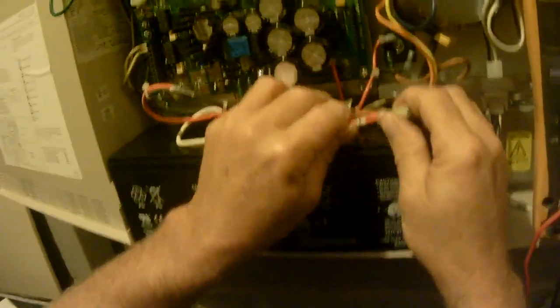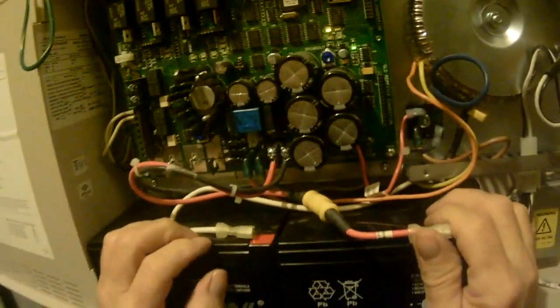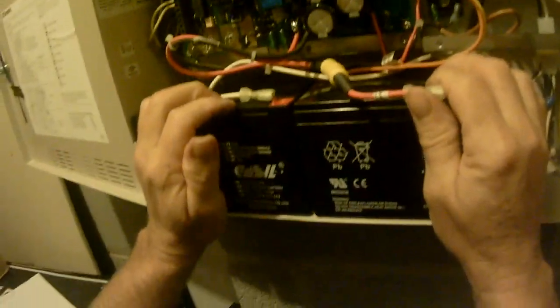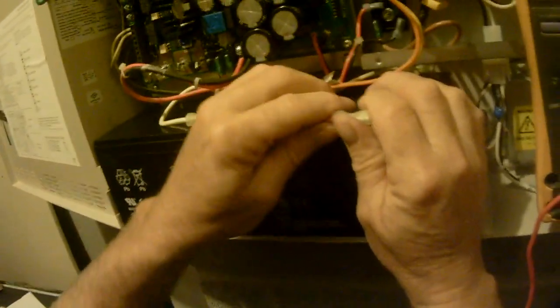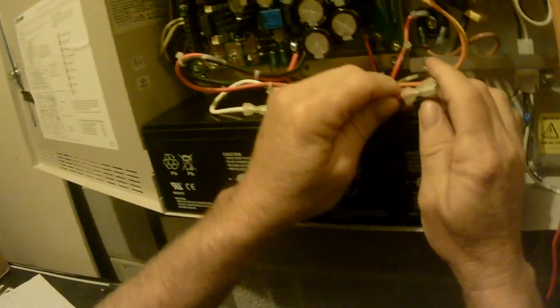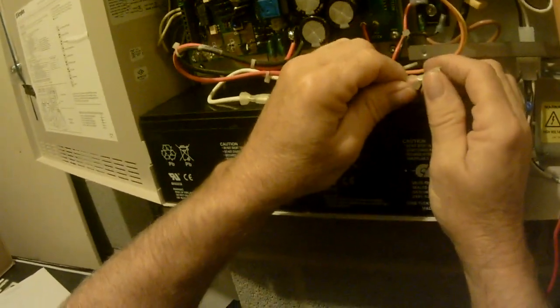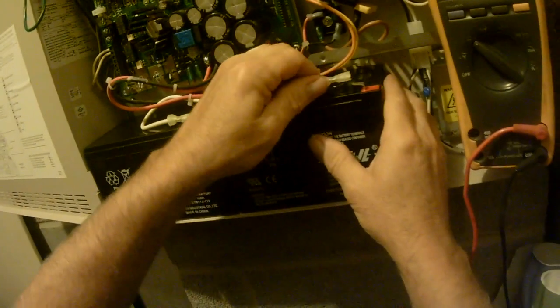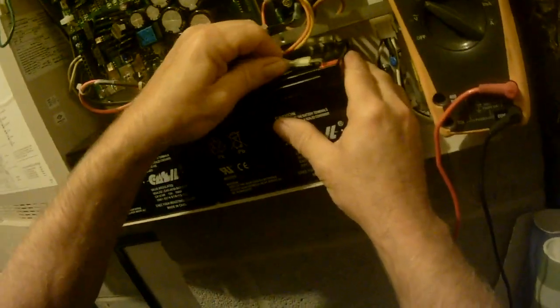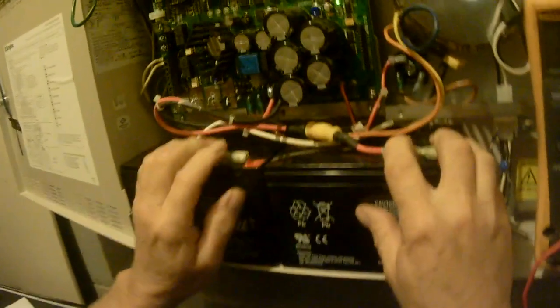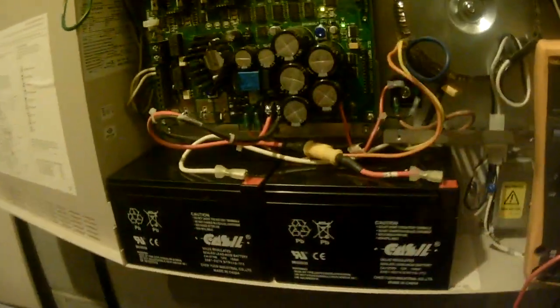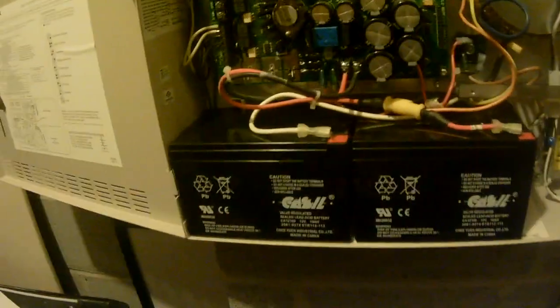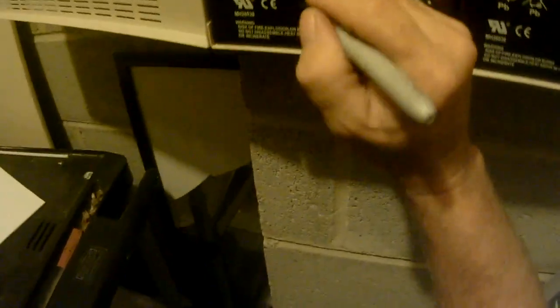If there's too much of a difference, it will say low battery. That's the ability to say the battery can't hold a charge. So you can have a low battery and still be normal because the panels test the integrity of the battery rather than just the voltage, but every 90 seconds. So when I hook this up, that light won't go out right away. We're somewhere in our 90-second cycle right now, but in a few seconds that should go out.